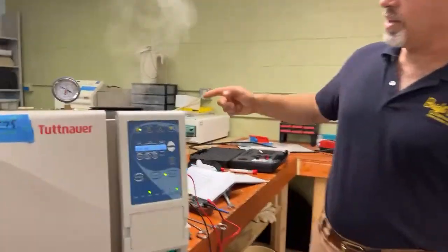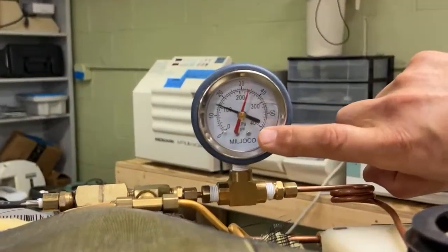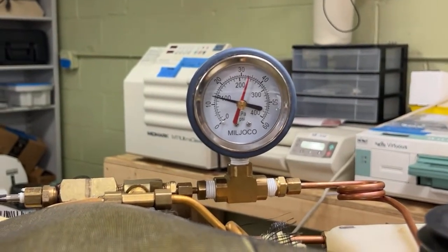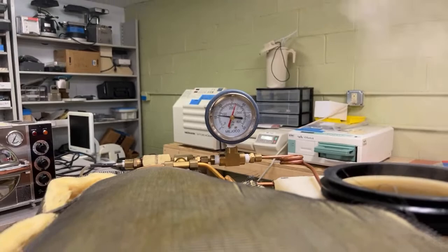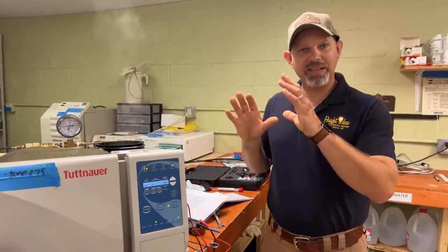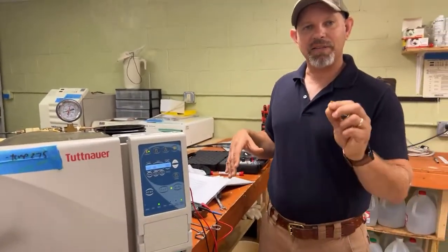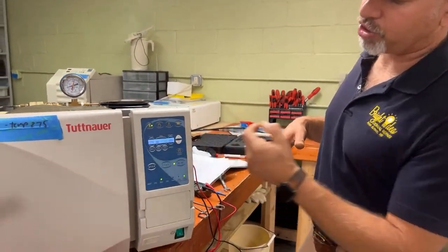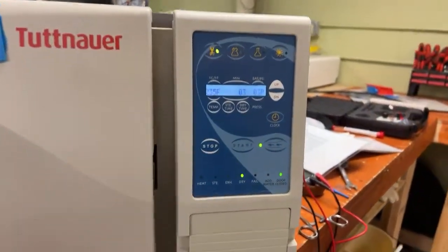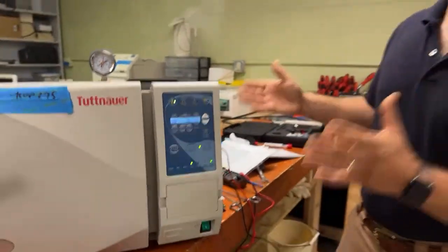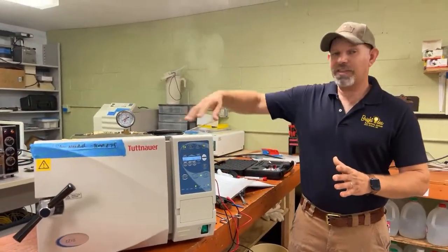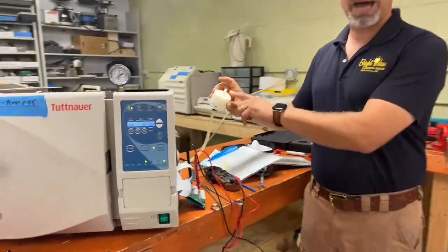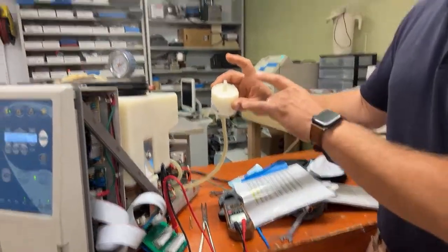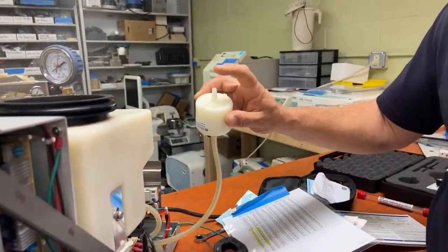As you can see, our gauge registered the pressure at about 32 pounds. It was reading about 31 on the gauge, and our temperature was good. It also looks like it's going to pass the cycle, which is a good sign. The thing we want to pay attention to now is that pressure goes back down to 0. That's the drying phase that I told you about. So the pump is running. That noise is air coming in through the HEPA filter. We can tell it's coming in through the HEPA filter because if I block that, the noise is going to stop.